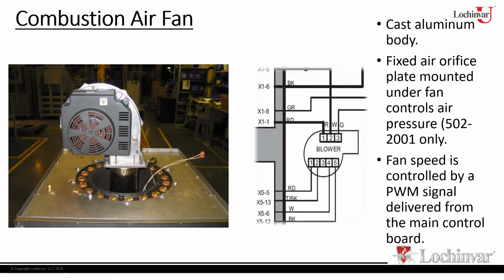So we have run into this as an issue on various products. If it's kind of a weird intermittent thing, check the externals. Is there something else tied in, or is there a safety possibly that's just bouncing power to it? So check your voltage, go through the wiring diagram, check your safeties, make sure there's nothing just pulsing power to the control module, okay?